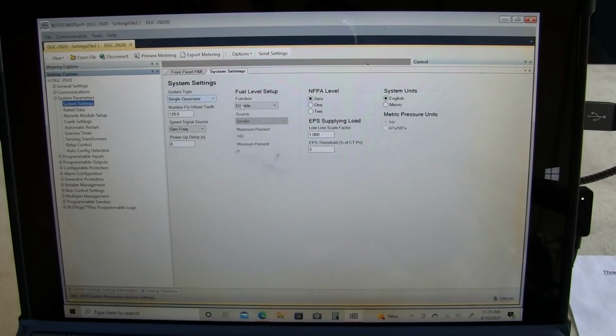System, single generator. Fuel level setup. This control panel can monitor a fuel tank for level. The NFPA level, which in this case is 0, refers to the regulations the generator would fall under. Level 0 is pretty much unregulated. Level 1, I believe it's worded as loss of life likely if the generator does not operate correctly. Level 2 is less a chance of loss of life if the generator does not operate. So pretty much anything in a hospital or a medical care center is going to be level 1.